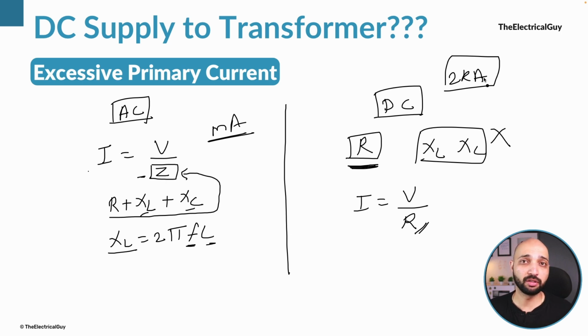The transformer will burst if you keep giving that supply continuously to the transformer. So very dangerous situation, and hence you must not connect any DC supply to the transformer, right? And it also depends upon the voltage source that you are connecting to the transformer. Let's say if you are connecting a 5 volt DC to a 500 MVA transformer, it's not going to have any impact, right? So it depends upon the transformer rating and the voltage source, a DC voltage source that you are going to connect to the transformer. It depends upon that, right?